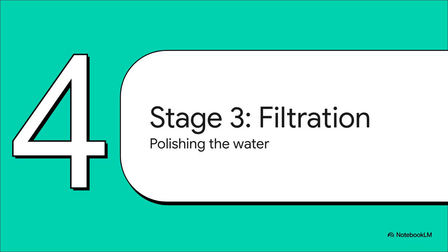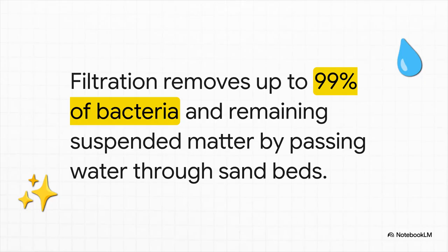Okay, after coagulation and sedimentation, the water is looking way, way clearer. But it's not quite ready for prime time yet. To get rid of the last little bits of fine particles and even some microorganisms, we move on to the polishing step, filtration. Filtration is an absolute powerhouse. Seriously, just by passing water through beds of sand, we physically strain out whatever is left. This pretty simple process can remove up to 99% of bacteria, so it's not just making the water clearer, it's making it a whole lot safer, too.